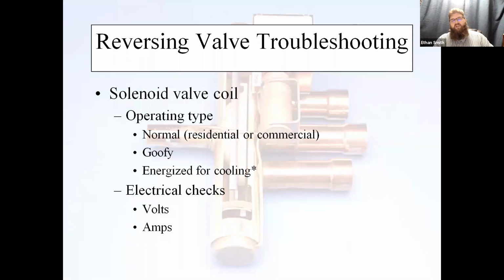Okay, reversing valve troubleshooting. You've got to know what kind of reversing valve you have. The old terms were normal and goofy valves. Normal valves is just what we call an energize-in-cooling valve these days, guys. Most of the domestic manufacturers energize in cooling. The thing to be aware of is just make sure that you know which it is. Some of the overseas units, some of the mini splits, will energize in heat. So make sure you know which valve you're talking about.